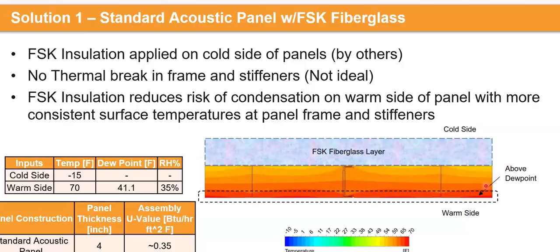Well, it would work. CFD shows that with installing this on your cold side, you do keep your warm side above the dew point. The dew point here would be 41 degrees Fahrenheit, and the warm side is currently at 70 degrees. So there would be no condensation on this particular system. It would, however, be very expensive. If you also think of critical environments where having exposed fiberglass is not recommended or is not approved, then you begin to run into issues where you're not able to apply this FSK to that system.